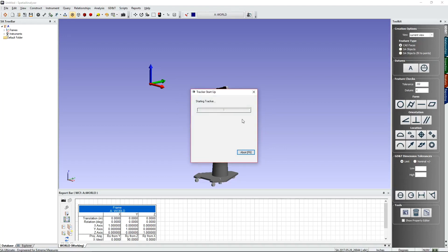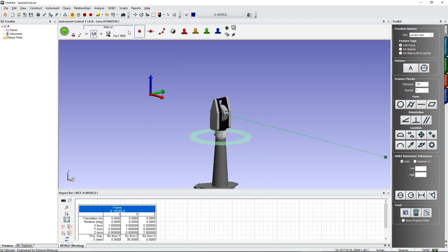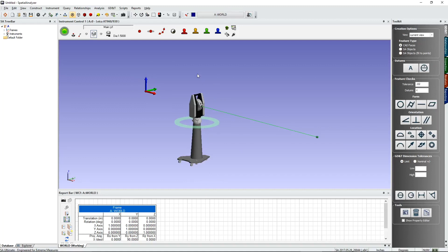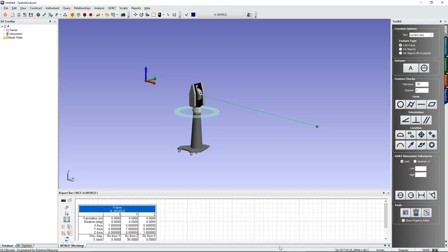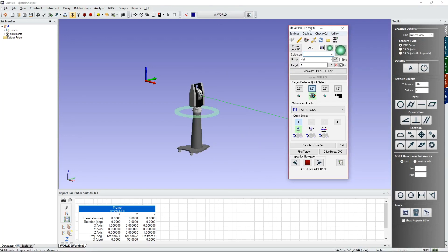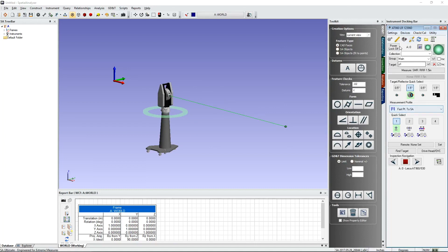Once you've started the tracker, you'll notice the instrument interface has two different looks. The most popular is the instrument toolbar, which contains all your most frequently used shortcut buttons. You can also switch to the standard instrument interface. The instrument interface is a separate window, but you can dock it inside Spatial Analyzer using the dock button, and toggle between the two views using that same icon.